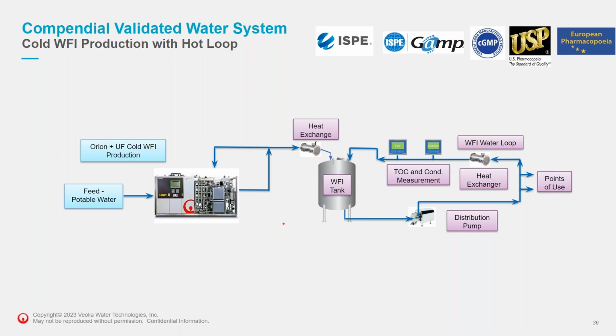Again, you would say, well, if I'm running hot distillation, why would I go to a cold WFI system? In terms of energy savings, because I've still got to heat the water up. Well, if you look at it, converting 1 litre of water to steam from 15 degrees C takes approximately 2,700 kilojoules of energy. Now, if this was a cold WFI system, we're producing water at, say, 15 degrees, and we sanitize at 85 degrees, so that's 70 degrees Celsius.